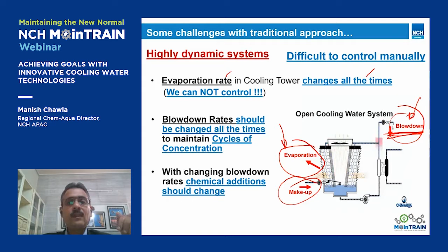Just see, if the cycle of concentration goes up, if we give less blowdown, the TDS goes up, the scaling tendency will increase, the solubility will reduce. But if we run it at low cycles, if we give too much blowdown, the water will become corrosive. In the same loop, your supply header temperature might be lower, return header temperature is higher, so the tendency will be different, right?